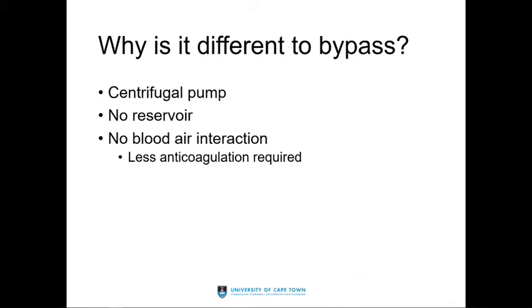Well, typically most bypasses were running roller pumps with a lot of red blood cell trauma as they compress the circuit. So these run as centrifugal pumps. There's no reservoir. It's a completely closed system. And there's no blood-air interaction, so there's less anticoagulation required.